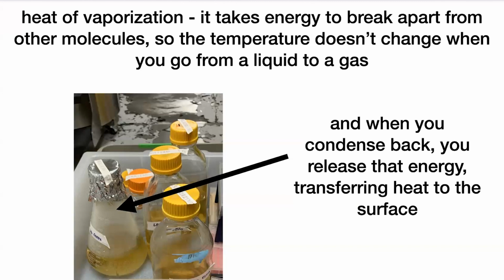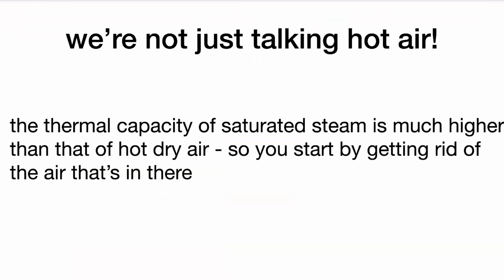When we're talking about an autoclave, we're not just talking about dry, hot air. It's really important that we have steam, because the thermal capacity of saturated steam, how much energy can be held in that gas and transferred to surfaces, is much higher than that of hot, dry air.